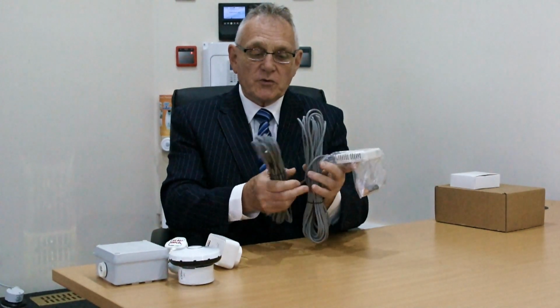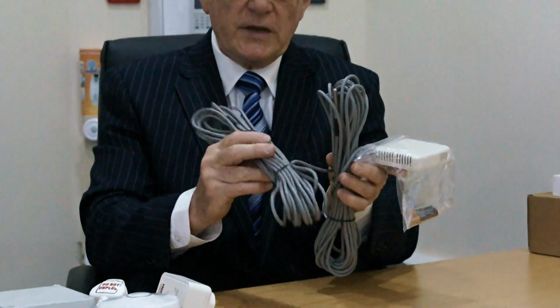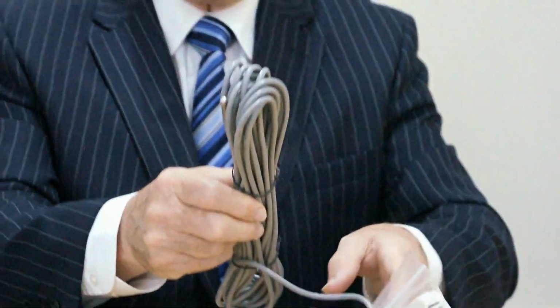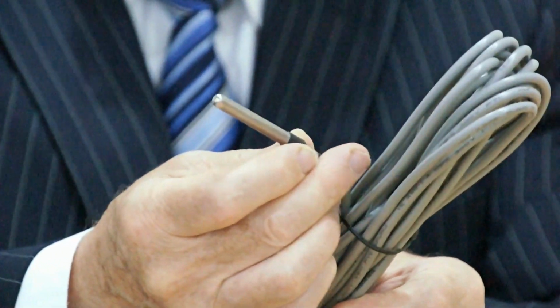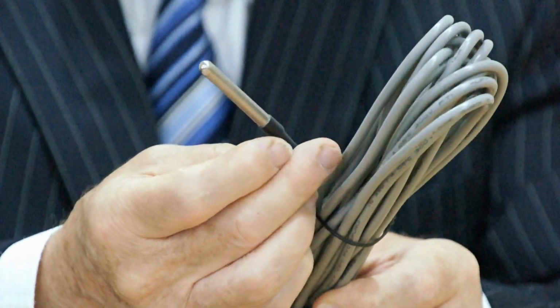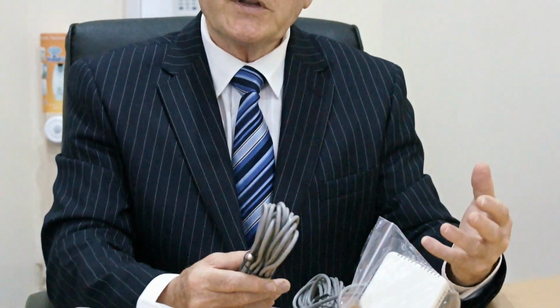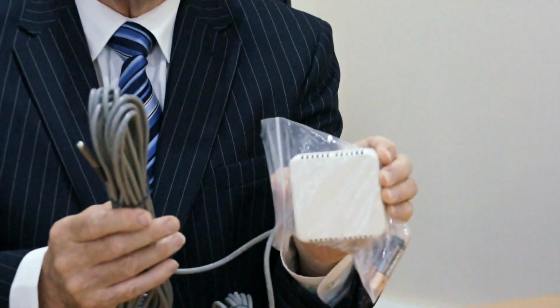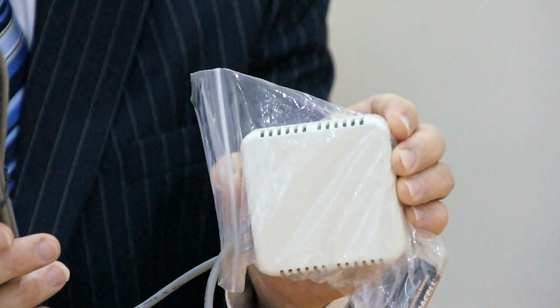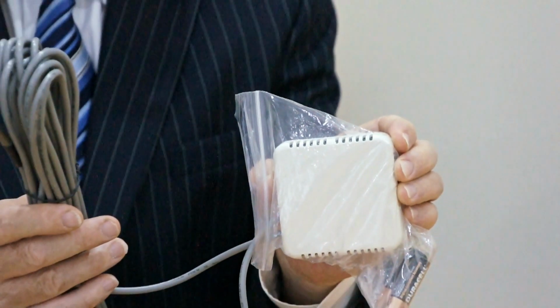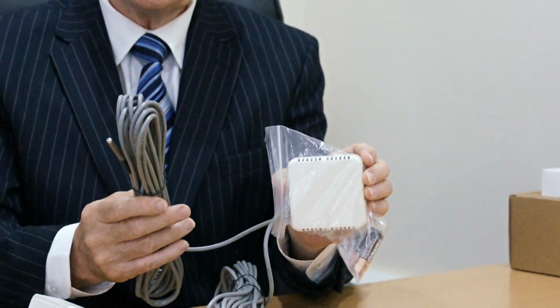We also have some more interesting sensors here. You'll notice these rather long pieces of cable - these are probe sensors on a long cable, with a stainless steel probe sensor at the end, and they're 10 meters long. It's possible to tie wrap these onto, say, pipes within a central heating system, so we can monitor the flow and return temperatures. This is connected to the wireless mesh network sensor, the Z sensor, which talks automatically back to the hub, the T3521 hub.